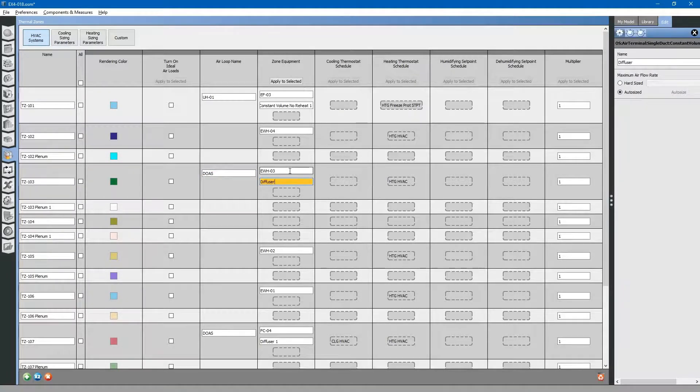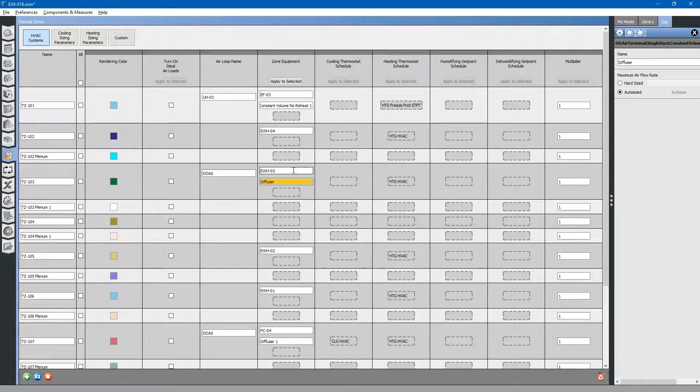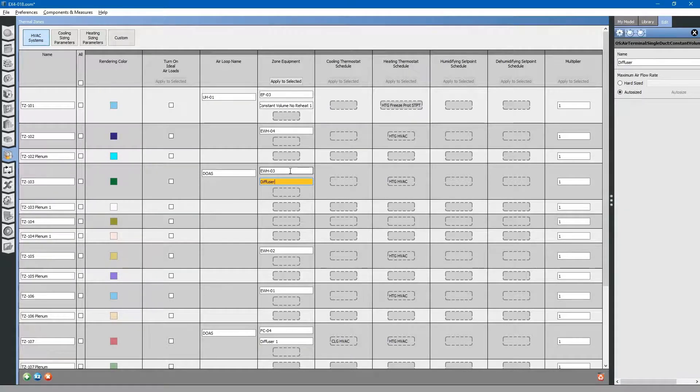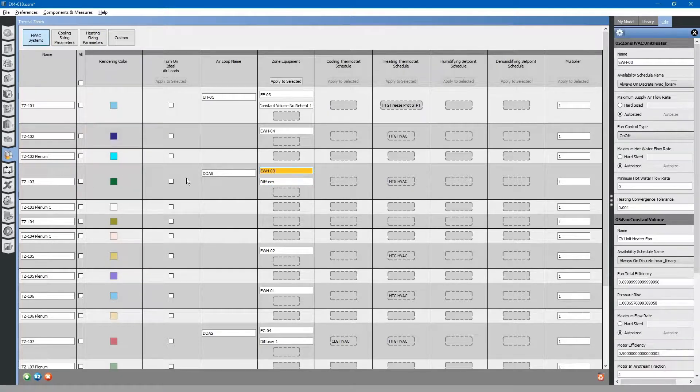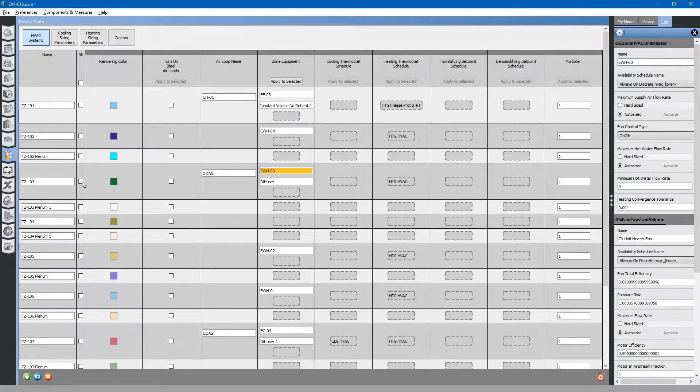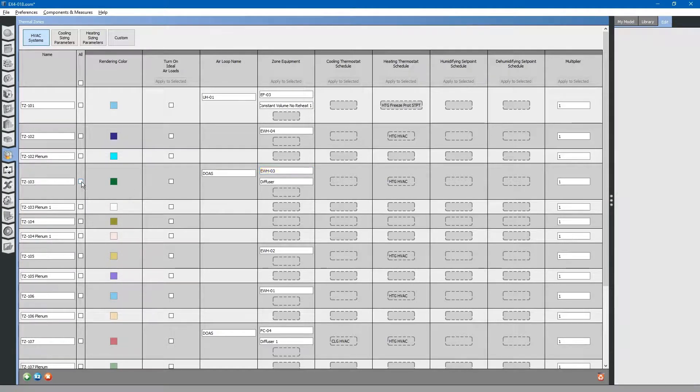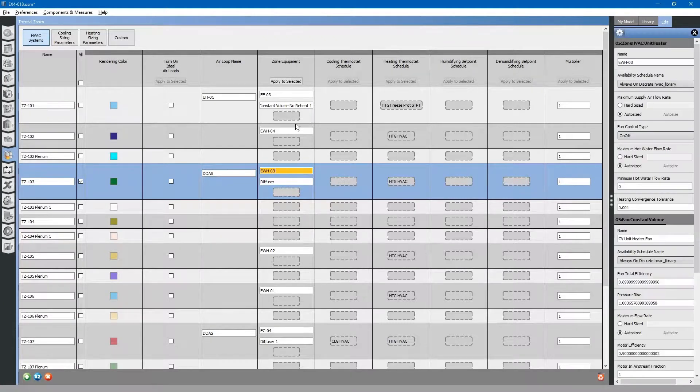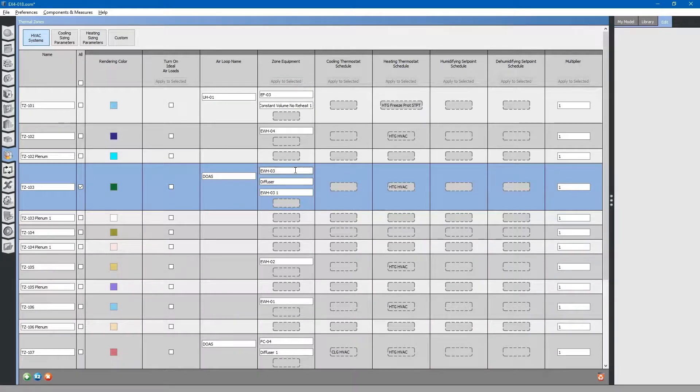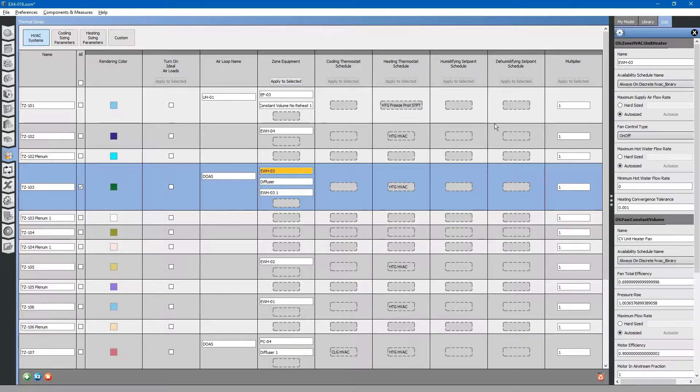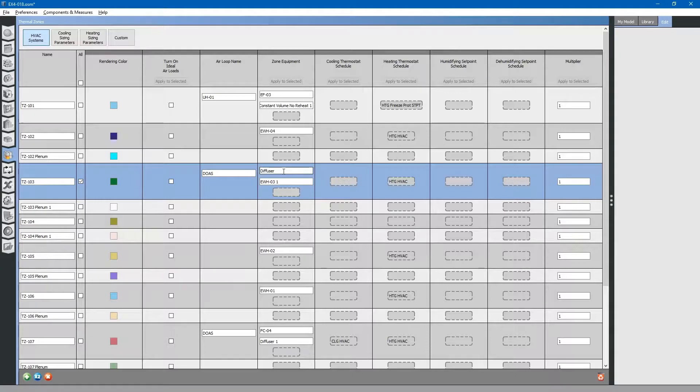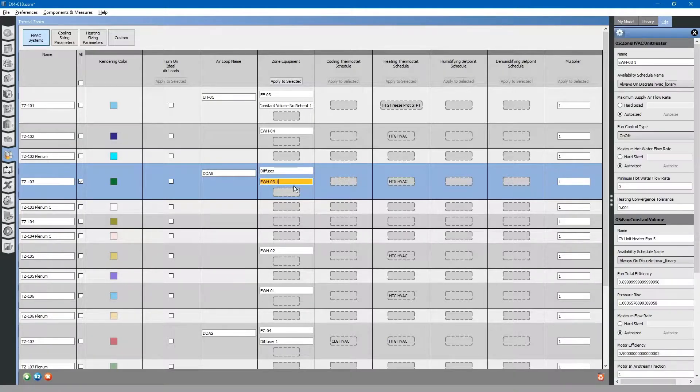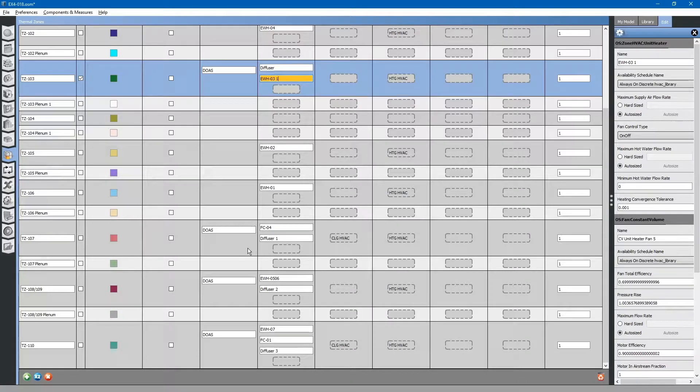You can see for thermal zone 103, the diffuser comes after the electric wall heater. But really, we want the heat from the dedicated outdoor air system to heat the zone first. Then the electric heater will take up any of the extra load. What we want to do is switch the place of these two. In order to do that, we can just copy and paste. Click the checkbox, select the wall heater, and hit apply to selected. This created a new wall heater. Then we can go back to the old wall heater and delete it. Now it will apply the dedicated outdoor air system heating to the space first. Then the electric heater will take up the additional load. We need to do this for all of the other systems as well.